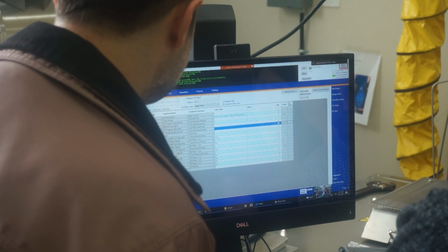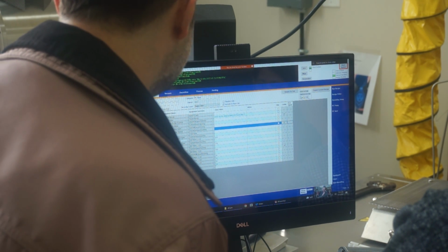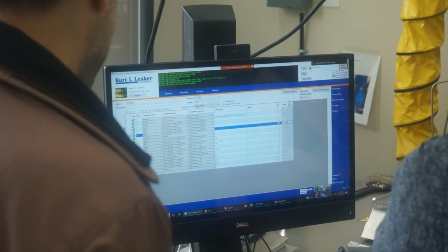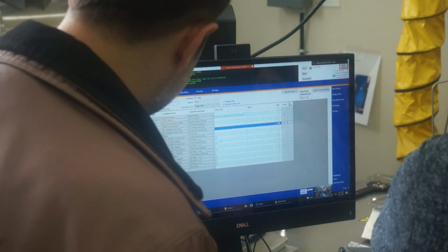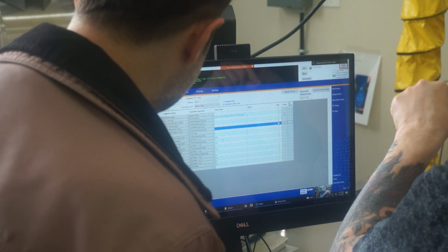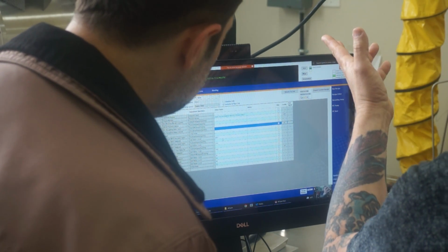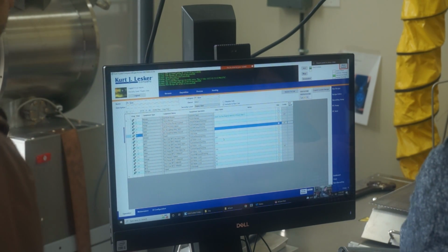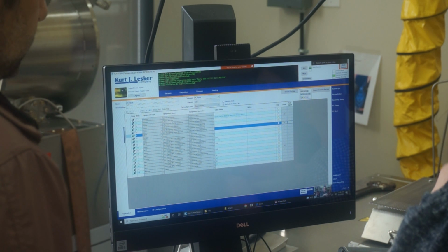And this sets the carrier gas flows, which the carrier gas is what vents this. On that chamber, you'll have a vent valve which vents up the chamber. The same carrier gas that's used for the process is also used for venting.